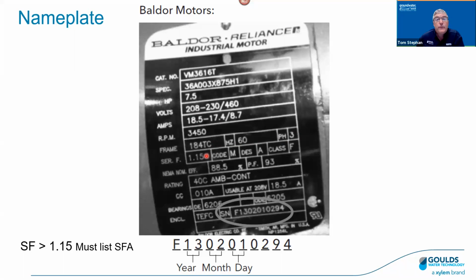Next we come to service factor. Just like the submersible pump that we looked at, this does have a service factor of 1.15. So we should see a service factor amperage value, or put another way, there are service factor amps, because if you have a service factor, you have service factor amps if you're into the service factor. But with this motor nameplate, service factor amps is nowhere to be found. Why is that? We can see here service factor greater than 1.15, which we don't have in this case. It's just 1.15.